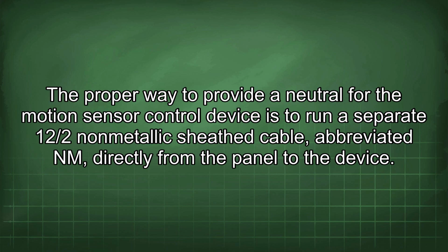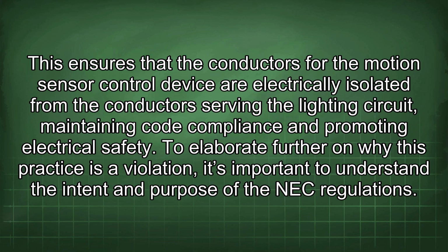The proper way to provide a neutral for the motion sensor control device is to run a separate 12/2 non-metallic sheath cable, abbreviated NM, directly from the panel to the device. This ensures that the conductors for the motion sensor control device are electrically isolated from the conductors serving the lighting circuit, maintaining code compliance and promoting electrical safety.